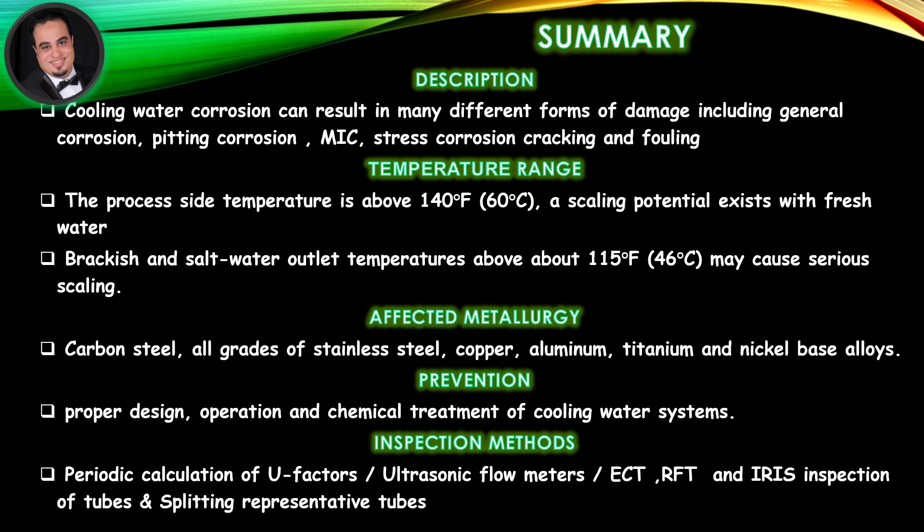Affected metallurgy includes carbon steel, all grades of stainless steel, copper, aluminum, titanium, and nickel base alloys. Prevention involves proper design, operation, and chemical treatment of cooling water systems. Inspection methods include periodic calculation of U-factors, ultrasonic flow meters, ECT-RFT, IRIS inspection of tubes, and splitting representative tubes.